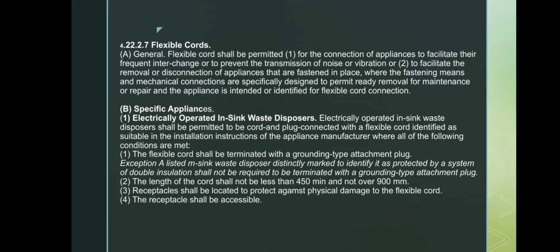Next, for electrically operated in-sink waste disposers, they may use a flexible cord and plug if the following conditions are met. Number 1. The flexible cord must end with a grounding type plug unless the disposer is listed as double insulated, in which case a grounding plug is not required. Number 2.